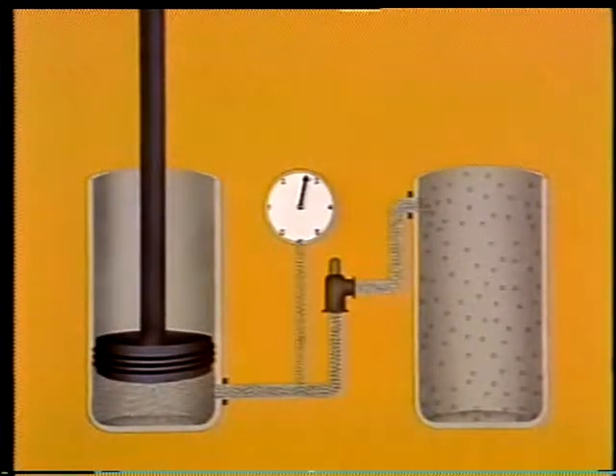Because of the way gases and steam act, putting a relief valve on a gas or steam system leads to two major problems. First, a relief valve opens gradually. It doesn't open quickly enough to let out the tremendous buildup of gas or steam causing the excess pressure.